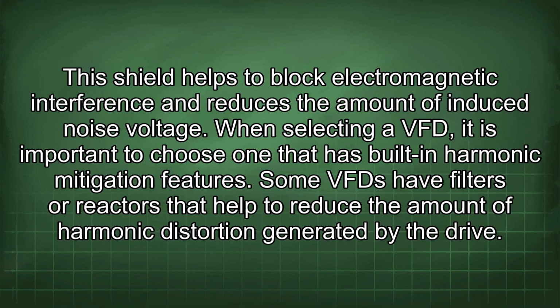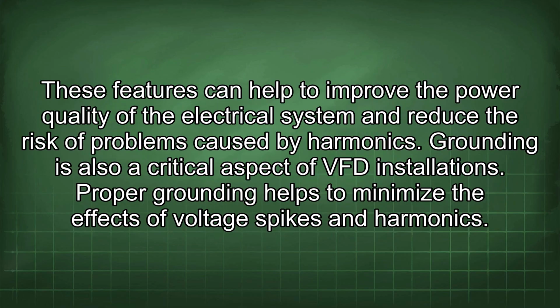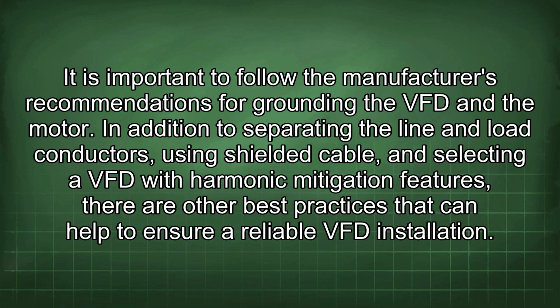When selecting a VFD, it is important to choose one that has built-in harmonic mitigation features. Some VFDs have filters or reactors that help to reduce the amount of harmonic distortion generated by the drive. These features can help to improve the power quality of the electrical system and reduce the risk of problems caused by harmonics. Grounding is also a critical aspect of VFD installations. Proper grounding helps to minimize the effects of voltage spikes and harmonics. It is important to follow the manufacturer's recommendations for grounding the VFD and the motor.